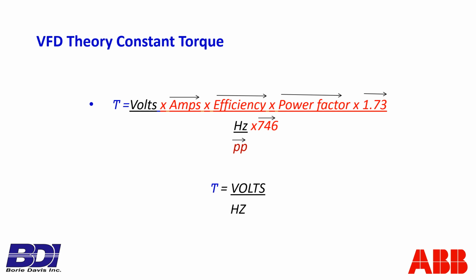Torque, electrically, in a three-phase AC system, therefore, is equal to volts times amps times efficiency times power factor times the square root of 3, 1.73, divided by hertz, frequency, times 746 watts per horsepower, divided by the number of pole pairs in the stator of the motor. So once you bolt that motor in place, if it says it's a 5 horsepower motor, well, that's what it is, 5 horsepower. And it's rated 6.7 amps, then that's how many amps it can handle, 6.7.